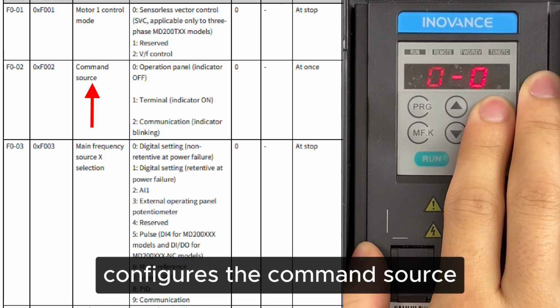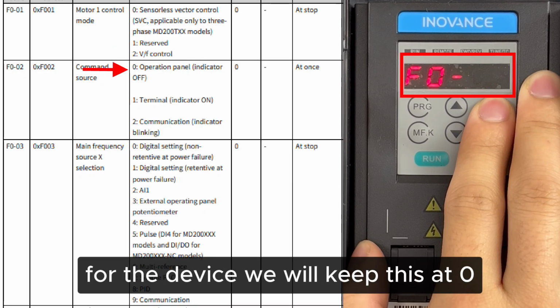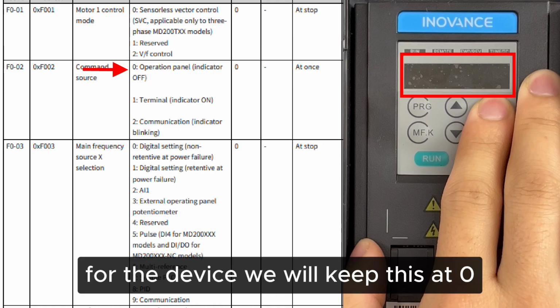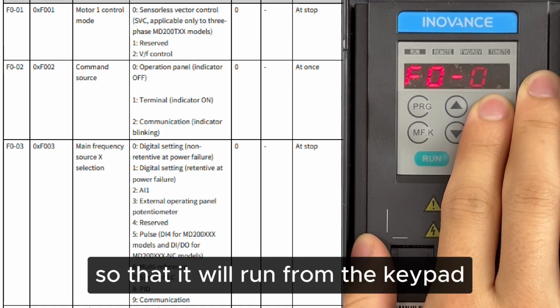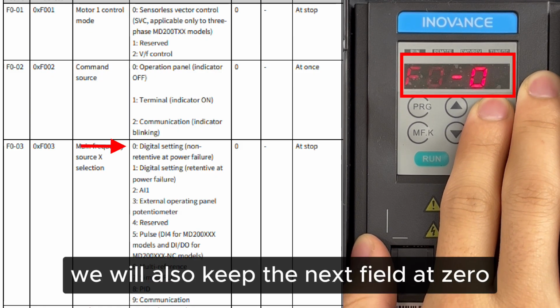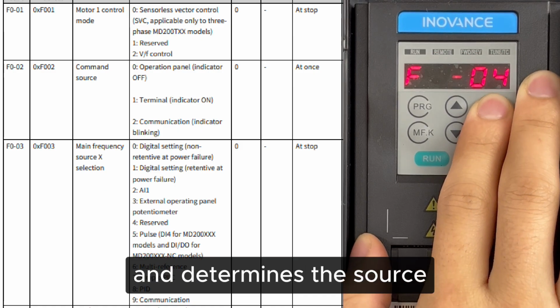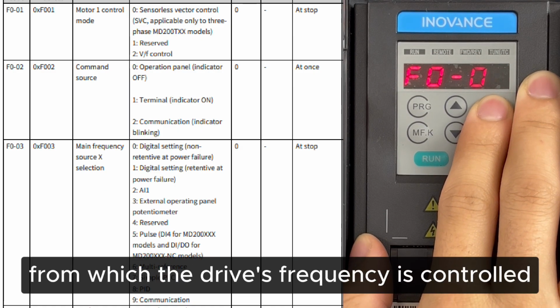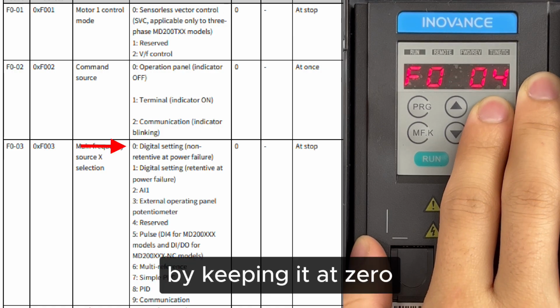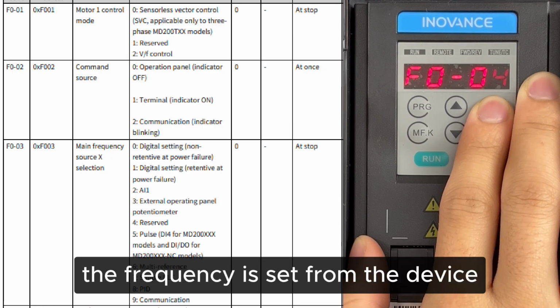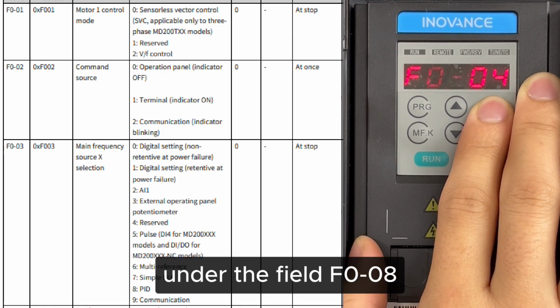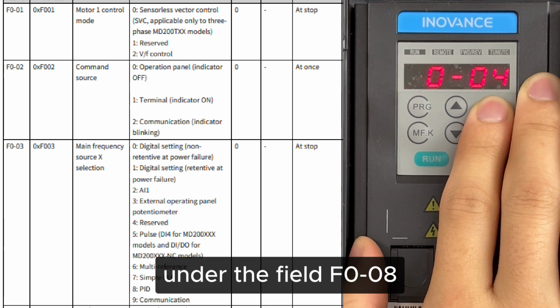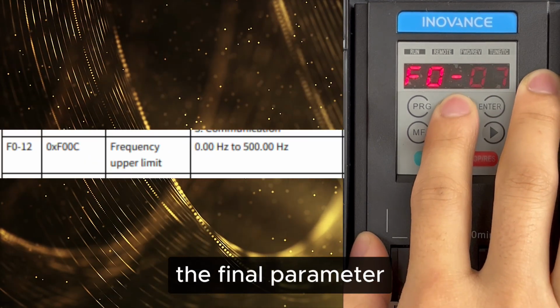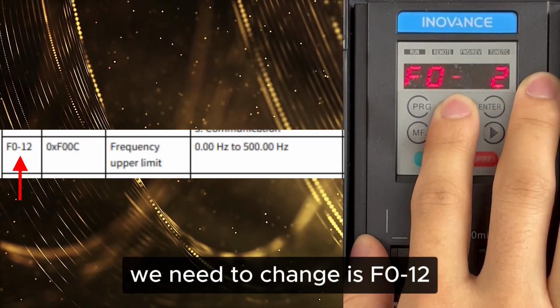The next field configures the command source for the device. We will keep this at 0 so that it will run from the keypad. We will also keep the next field at 0. This parameter is the frequency source and determines the source from which the drive's frequency is controlled. By keeping it at 0, the frequency is set from the device under the field F0-08. The final parameter we need to change is F0-12.